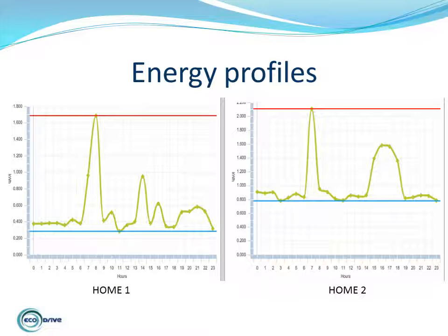The energy profile shown in the slide is of two different domestic installations on the Sunshine Coast of Queensland. Home A has a grid PV system sized at 1.5 kilowatts and Home B has a 3 kilowatt PV system. At the time the arrays are generating maximum energy, the installations are consuming their least. For self-consumption to happen for each installation, either the array needs to be downgraded or the energy generated from the array is stored and used at a different time, most effectively at peak times.